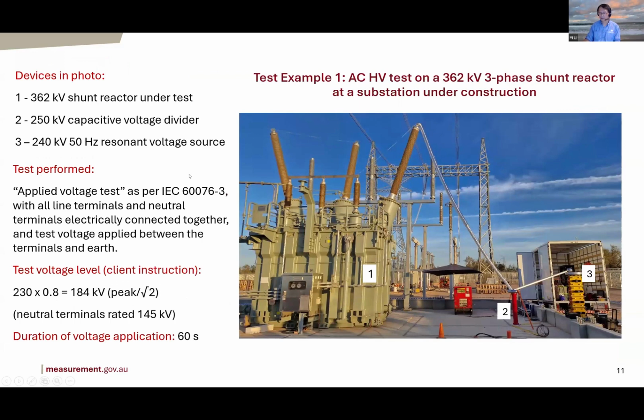So how do we generate, first of all, these high voltages? This is an example of how this voltage is generated. This is a short shunt reactor, 330 kV, 362 kV, and it needs to be tested for voltage withstand under AC voltage at that level. So in this test circuit, what we say quite often is that the test object is part of the voltage generation circuit. You can't generate the voltage without the test object, not like a calibrator. It doesn't matter what is connected, simply because it's a very heavy load.